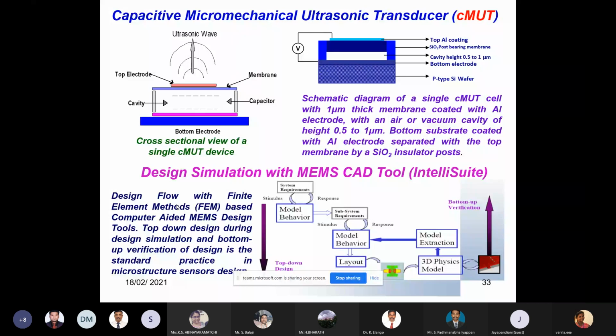Here, simply, the right hand side shows a simple structure. Bottom surface, air cavity, the light blue color is the insulating pillar. The top one is a membrane. The light blue color is an aluminum coating on the membrane for electrical contact. In the same way, the bottom also has an aluminum coating. Between these two electrodes, if you are measuring, you can measure the capacitance. Suppose you are applying a DC potential between these two electrodes, what will happen?